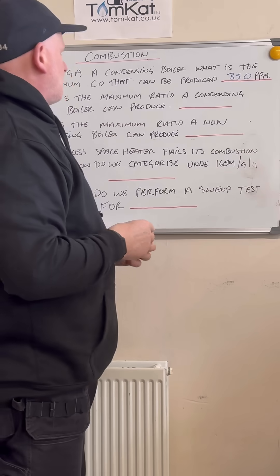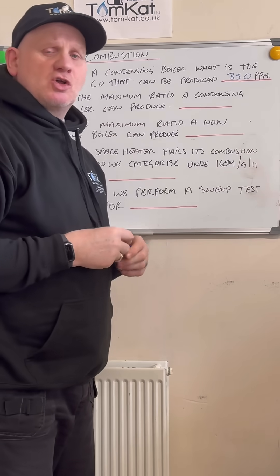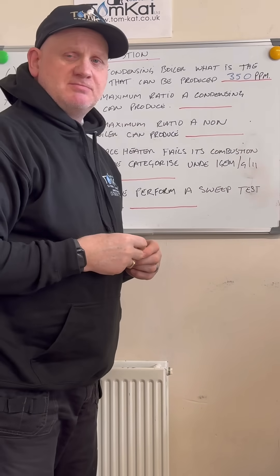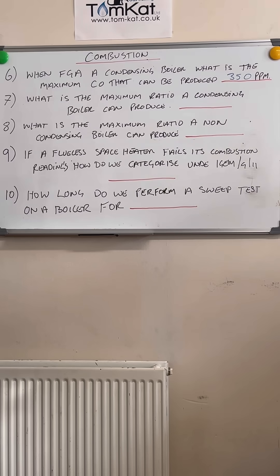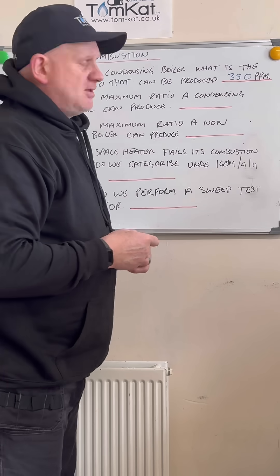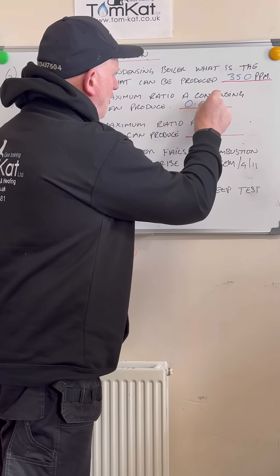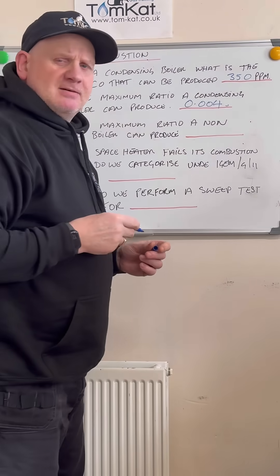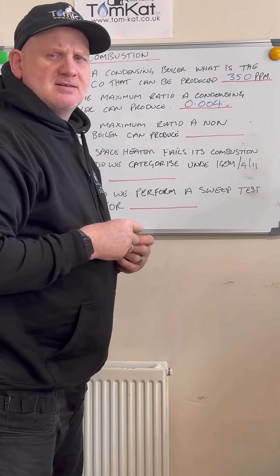Let's have a look at question seven. What is the maximum CO/air ratio a condensing boiler can produce? Did you say 0.004? Well, if you did, you'd be correct.